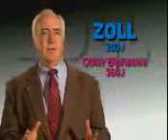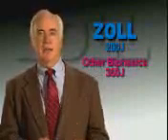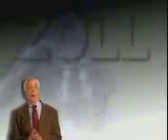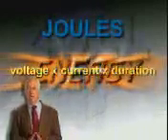Energy settings can be misleading. Higher joules don't necessarily translate into higher efficacy. The crucial component when you defibrillate patients is average current, especially crucial for high-impedance, hard-to-defibrillate individuals. Energy is simply the work required to deliver average current to the heart — the product of voltage times current times duration. So it's possible to have the same energy just by increasing duration and actually deliver less current to the heart.